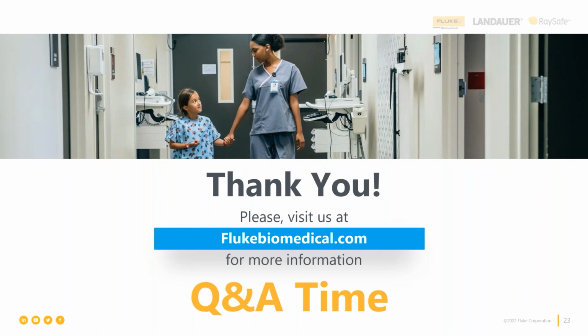They're specially designed for the purpose. If you want to be a design engineer, go do that. But if you're going to be a hospital-based biomed or field service engineer, your job is to test what you have using the appropriate test equipment. Yeah, I'm not saying you can't, you can, but now you're bearing more responsibility than you should, because did you improvise that test load correctly? Are you doing the test exactly in compliance with the testing methodology prescribed in the international standard? My guess is you're going to miss.